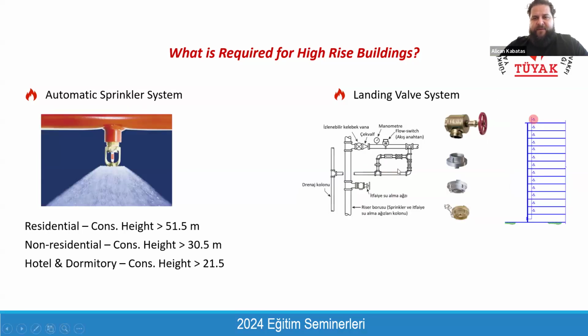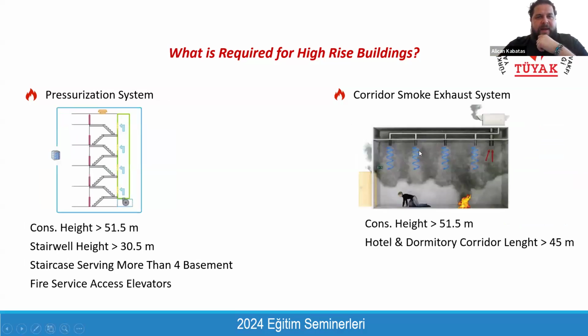And we have landing valve system for the high-rise buildings. It is located within the staircase. It means while you are designing the staircase, you should find a place to locate the landing valves. Otherwise, it will cause you a problem during the coordination of the systems.